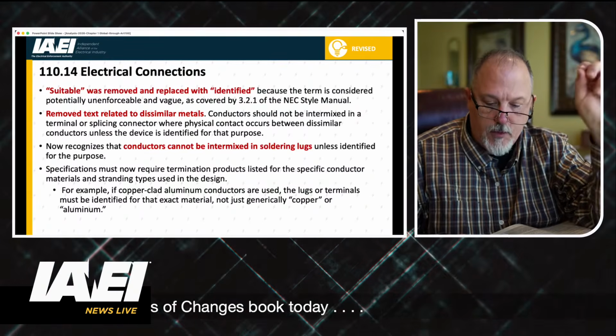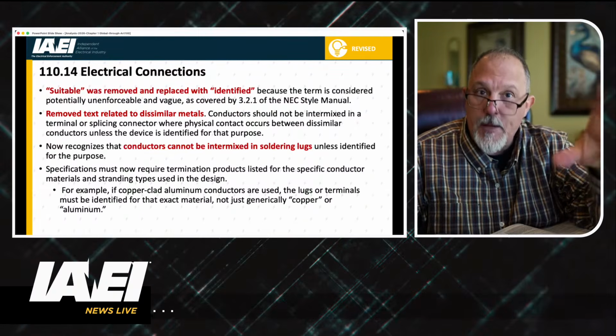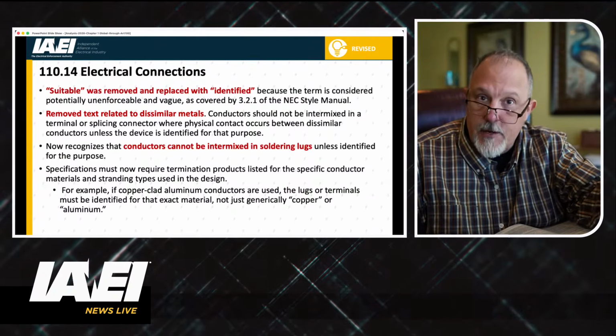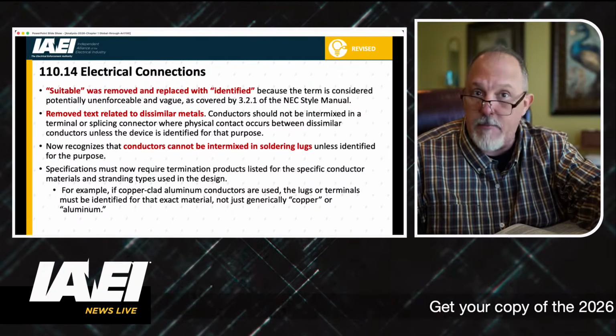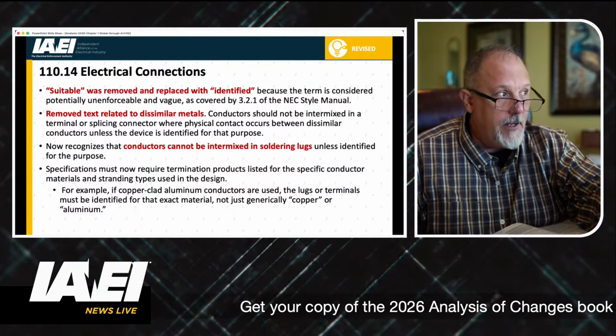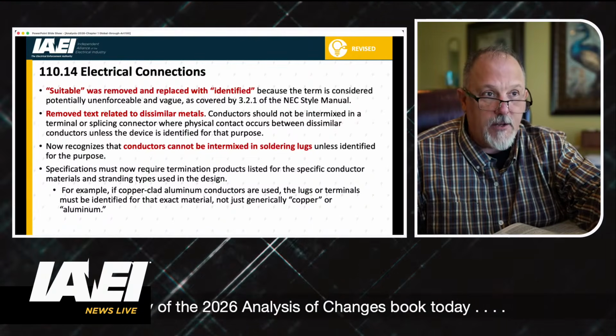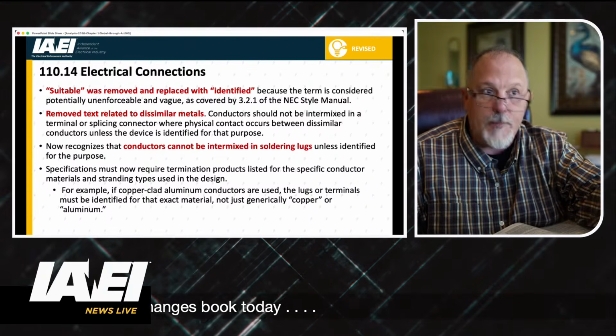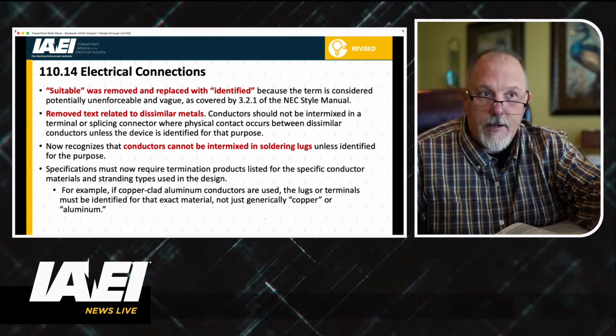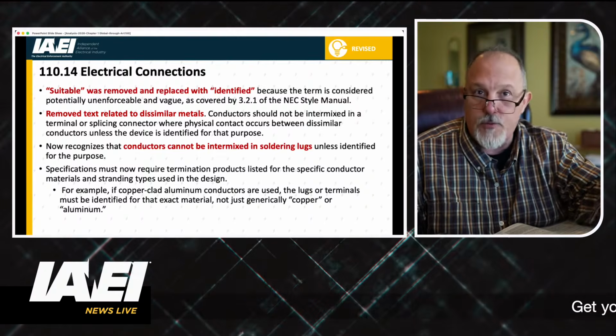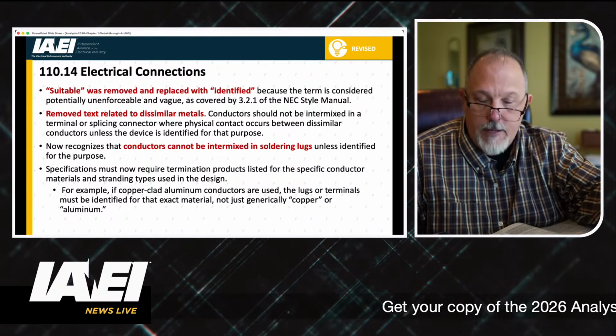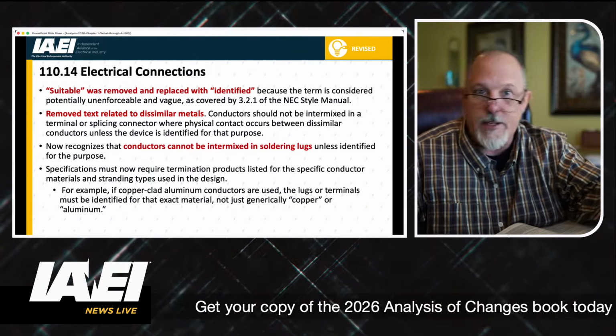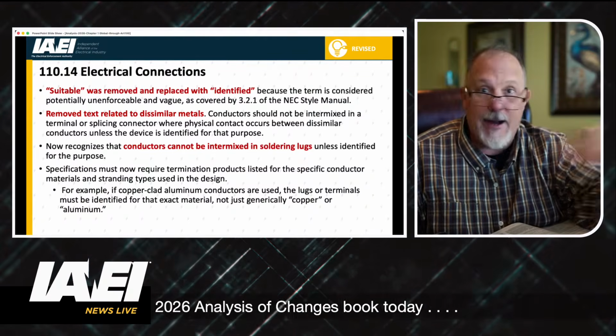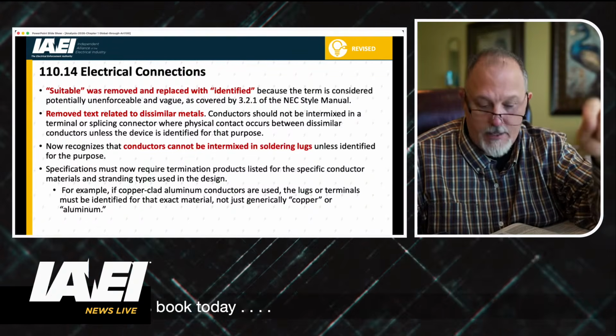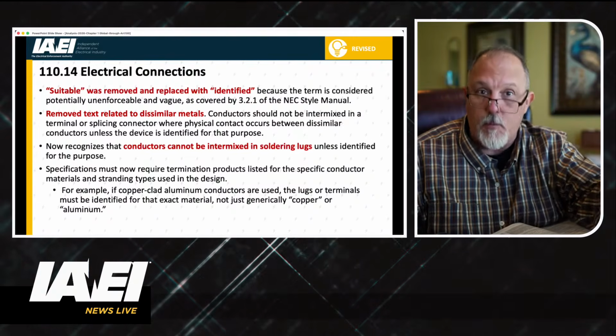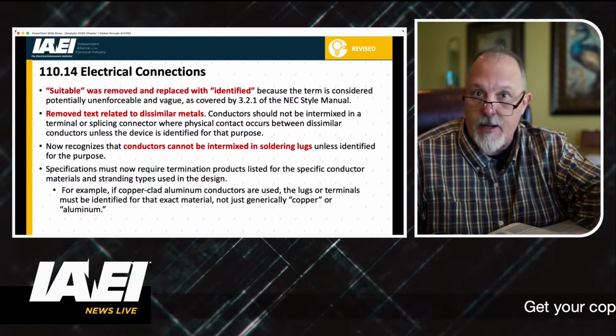So connections, we deal with terminals, we deal with the type of conductors that can be placed under there, whether it be copper, aluminum, dissimilar metals. That's a whole other thing. I know over the last couple cycles, the copper clad and the copper and the aluminum people have been clashing their swords around trying to add clarity with regard to what is a dissimilar metal, what is not a dissimilar metal, all that jazz. I'm not here to get into any of that. All I want to tell you is 110.14 is the home where you will learn what you can and can't do.